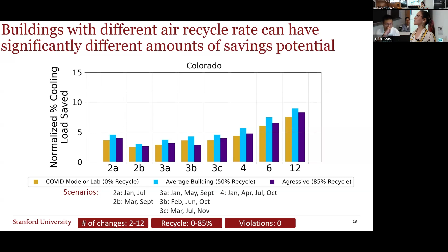So in conclusion, there is significant potential for low-cost energy savings from updates to these set-it-and-forget-it parameters, especially for older buildings with limited HVAC controls. These savings are both location and time dependent, as we've seen, and the results are for buildings that don't have a building automation system. The savings are robust across different locations, recycle rates, and numbers of allowed violations.